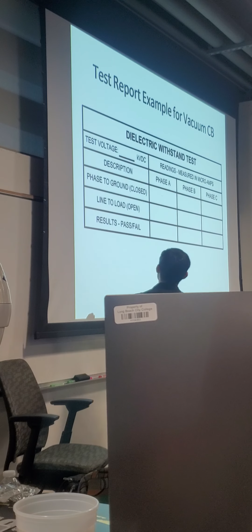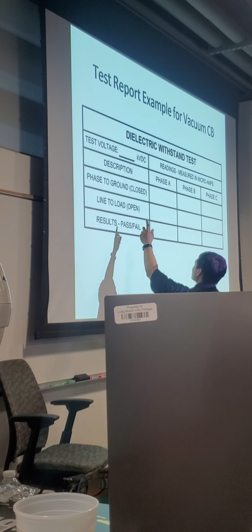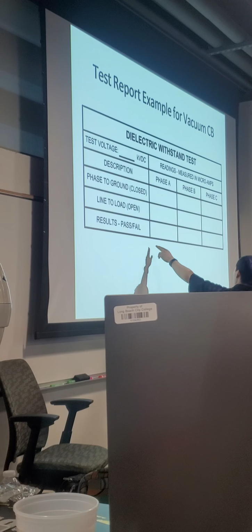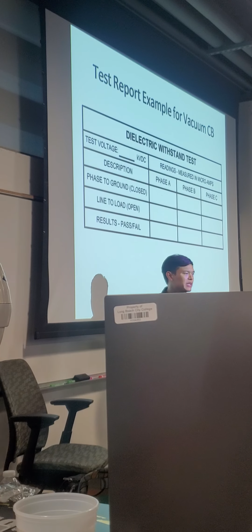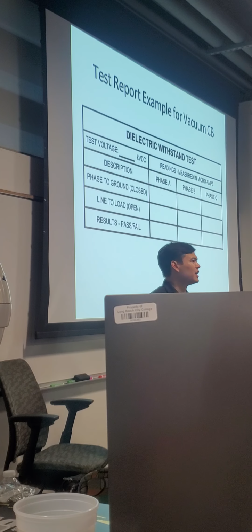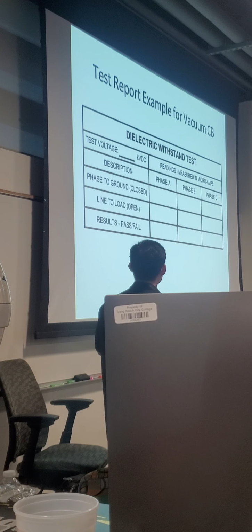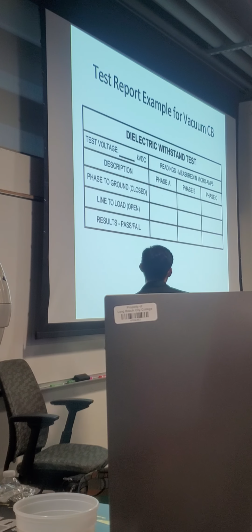Say B phase passes phase to ground but fails line to load, what would you put for the final determination? Fail. So if it fails any of these tests, it fails all. Basically, a fail in any of these configurations is a fail for that particular test.